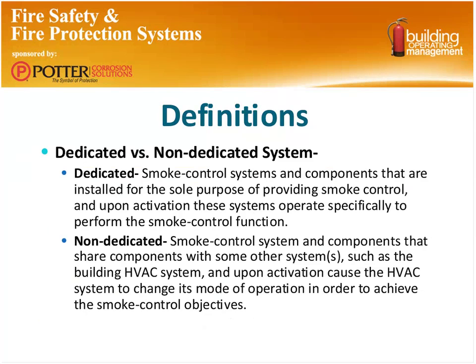A few more definitions. We have two different types of systems that we typically work with, one being a dedicated system, and that's dedicated strictly to smoke and fire control. Non-dedicated would be a multi-purpose dampering system where it's partly working with the HVAC system for air control in general, and also can be controlling the spread of smoke and flame.